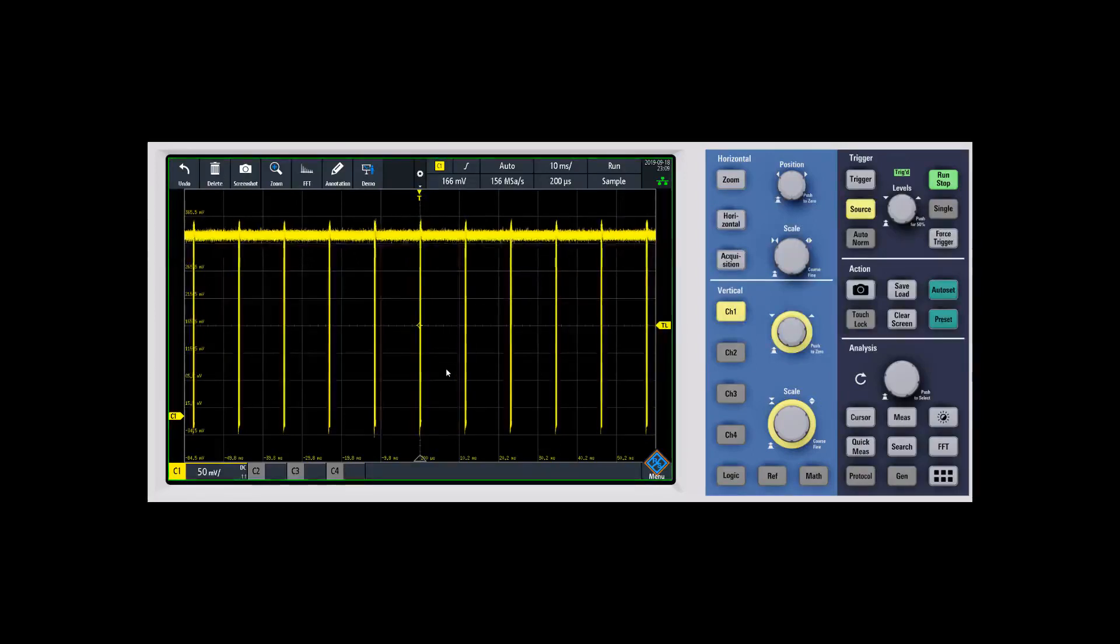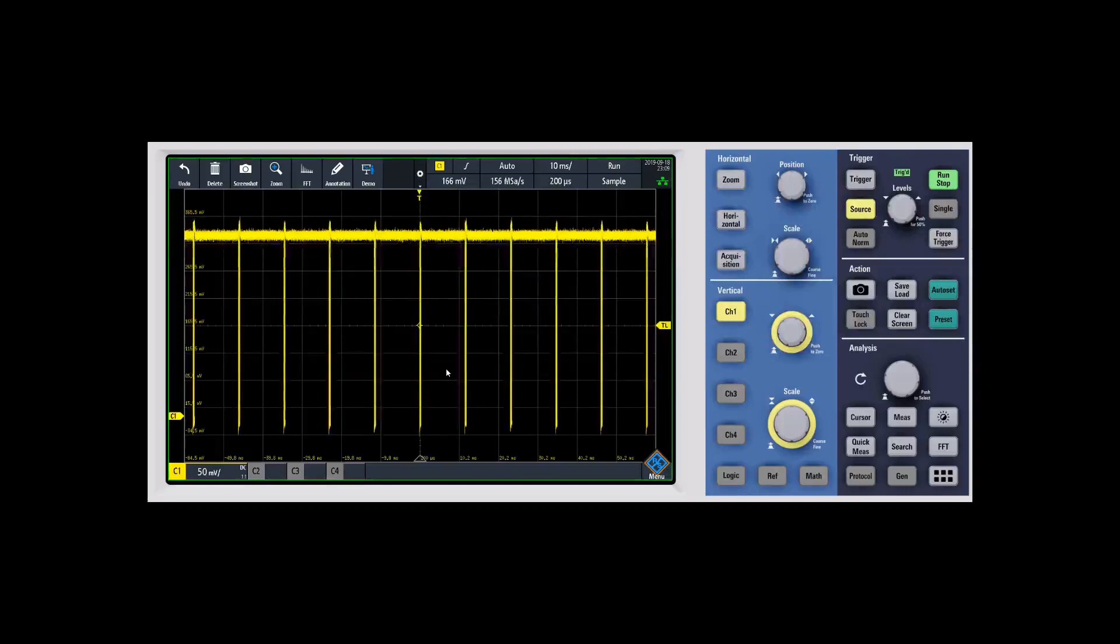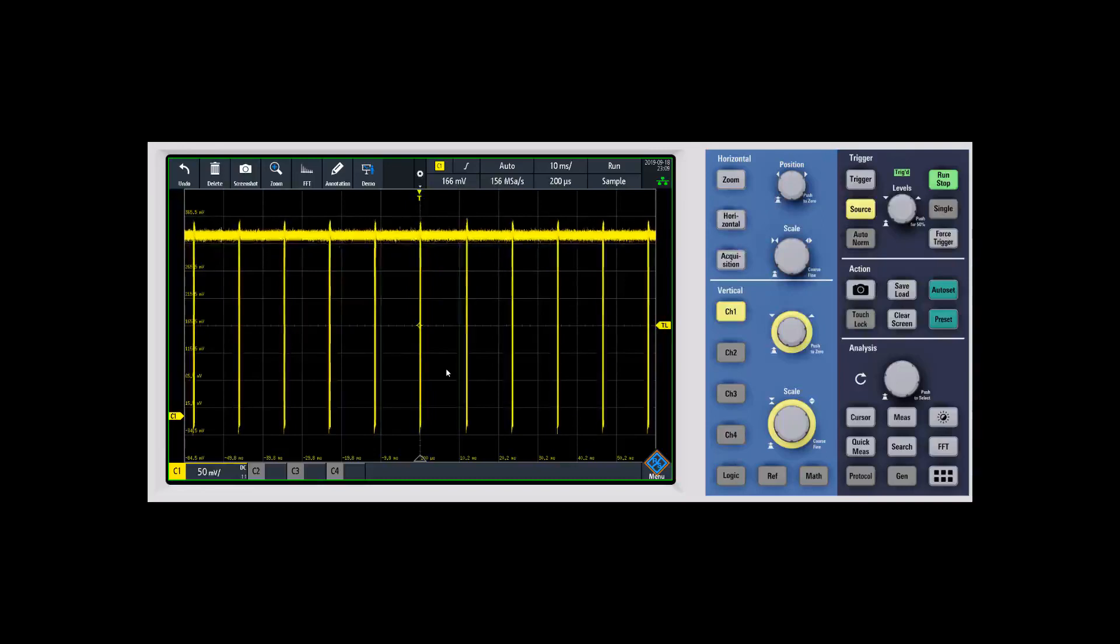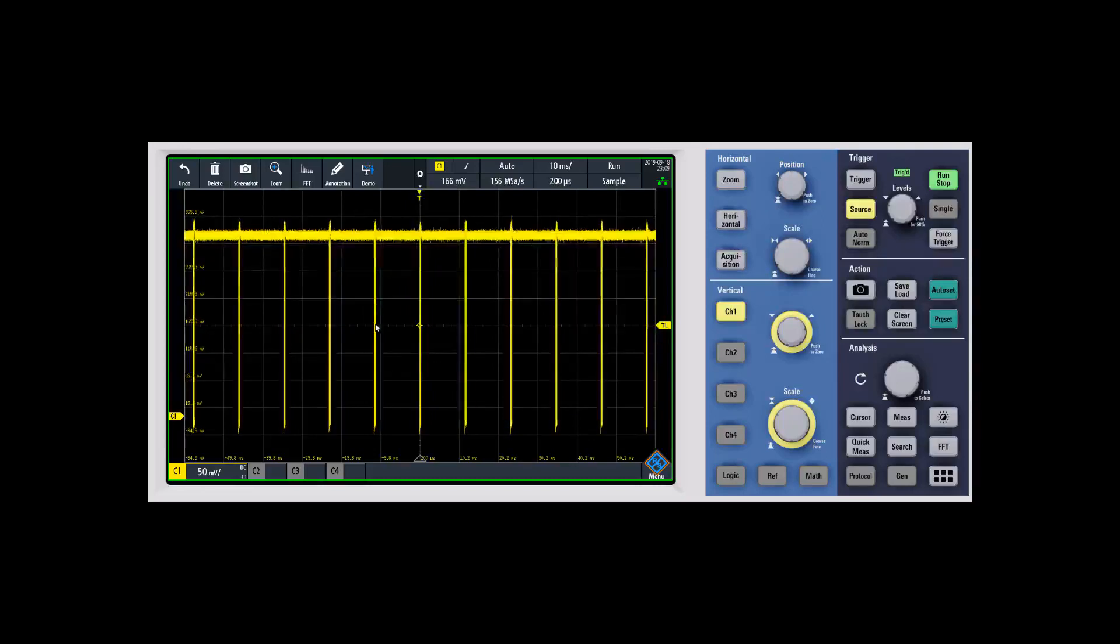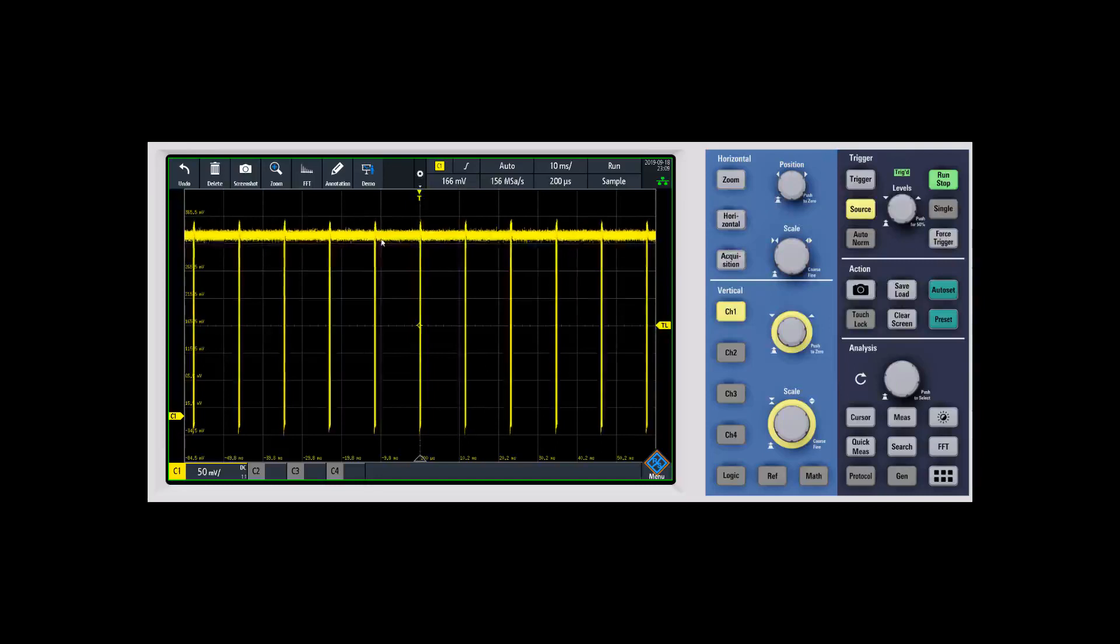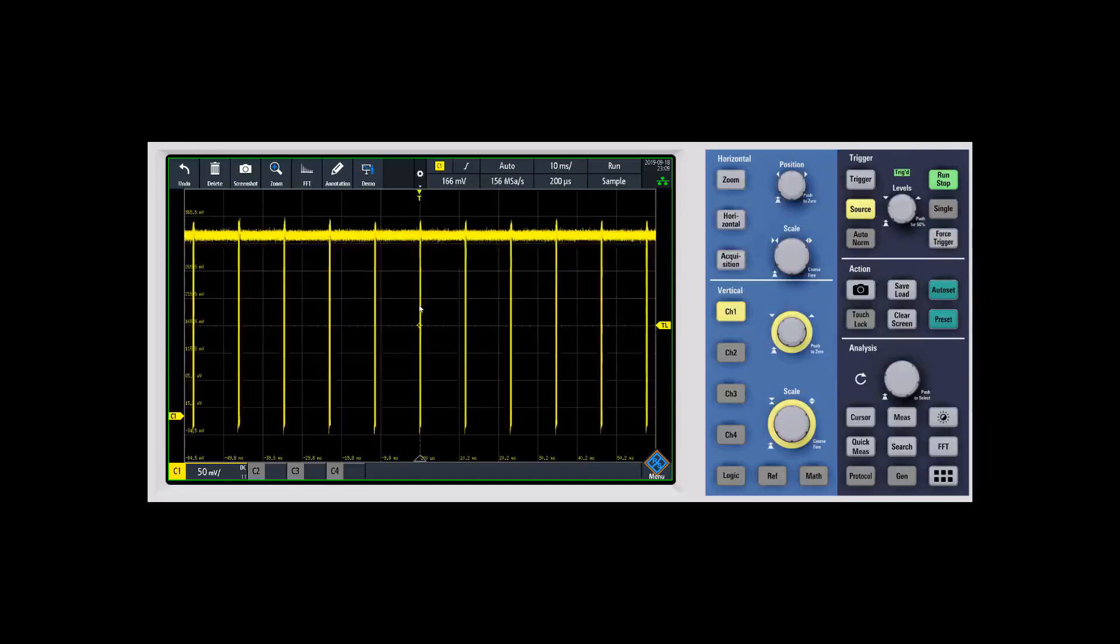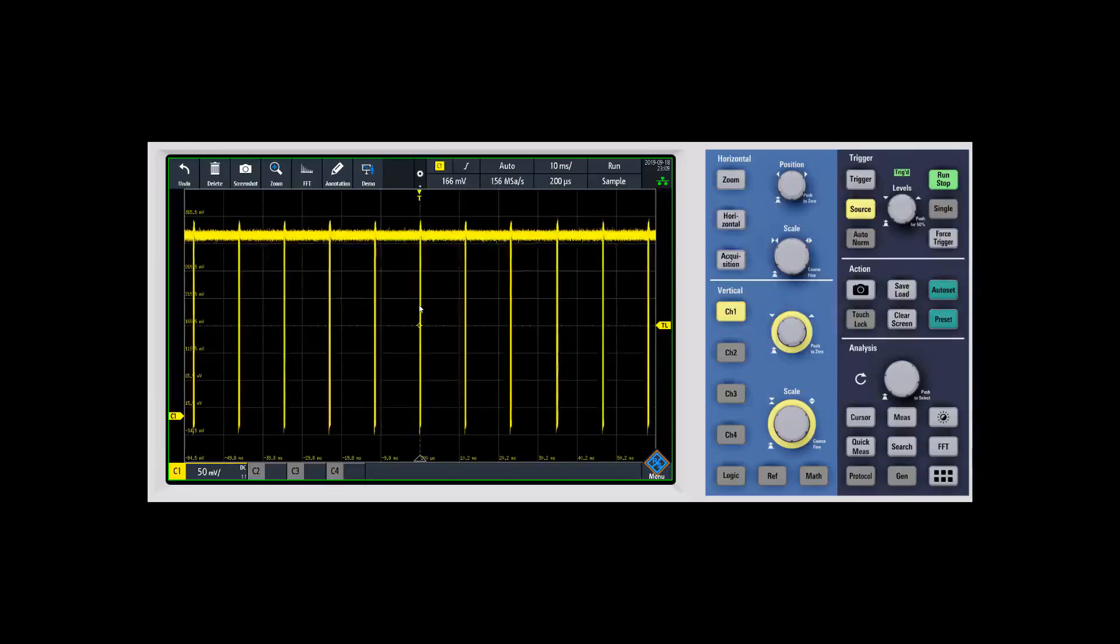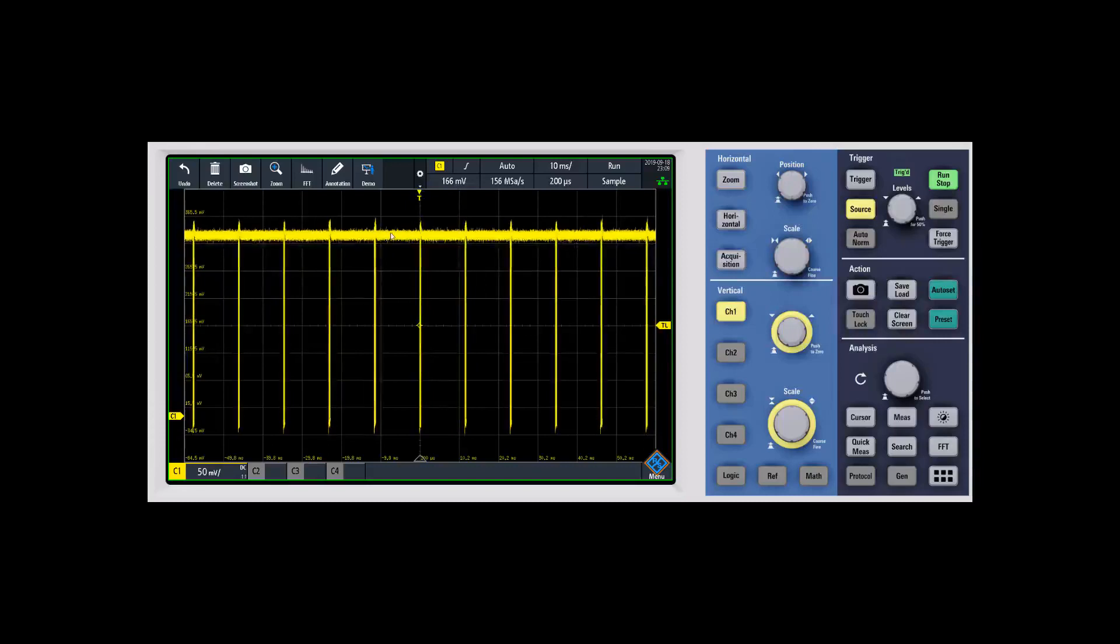This is a really good example of when you might want to use history mode. Segmented memory is really powerful for bursty signals. As you can see here, we have a signal where there's a burst or packet of information, then a fair amount of idle time, then another packet. You may not want to digitize and capture all that idle time.